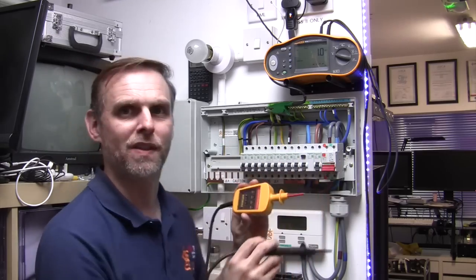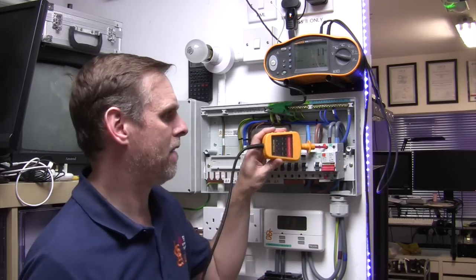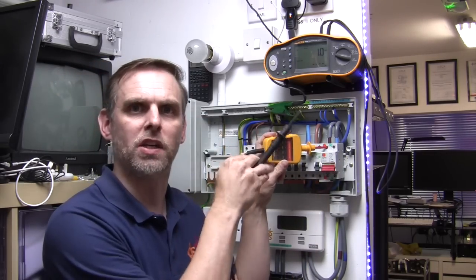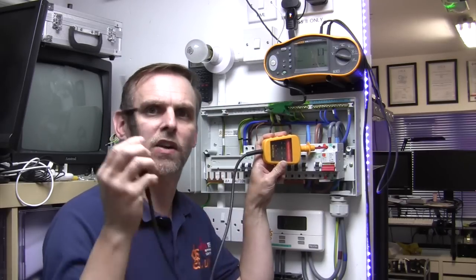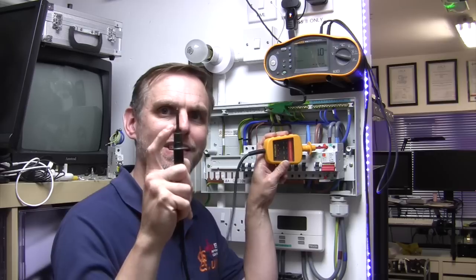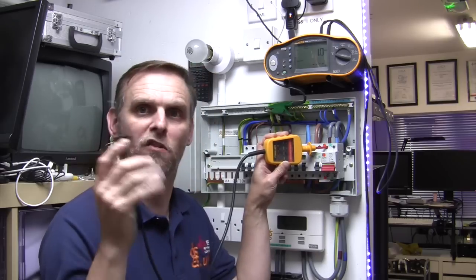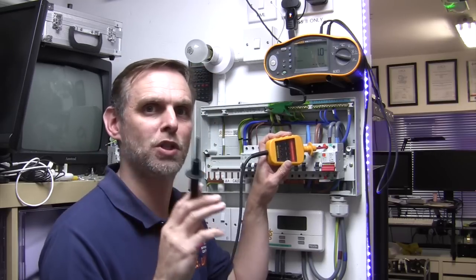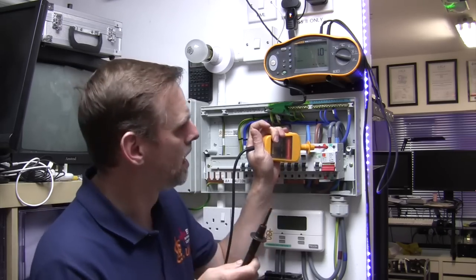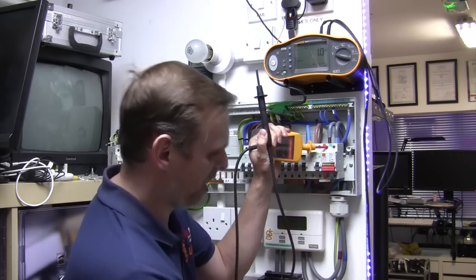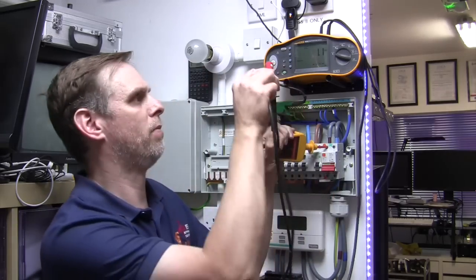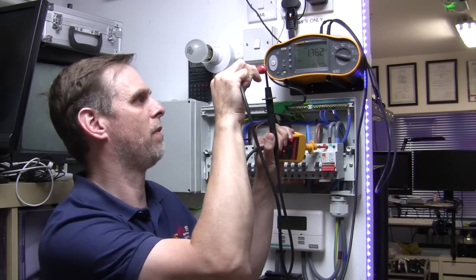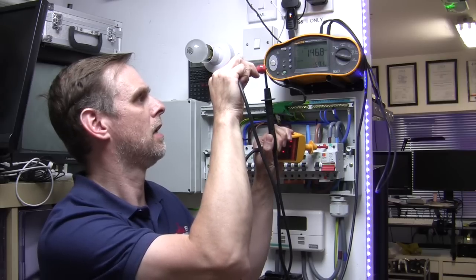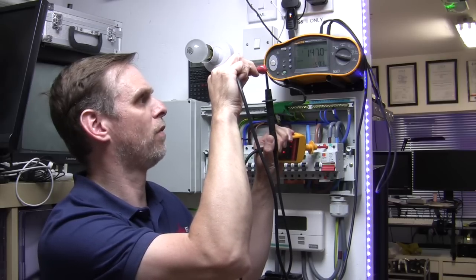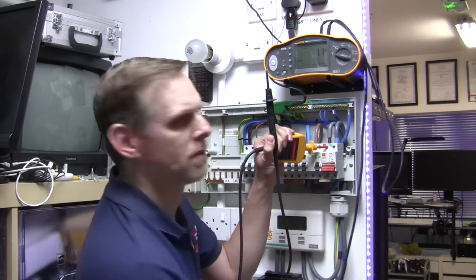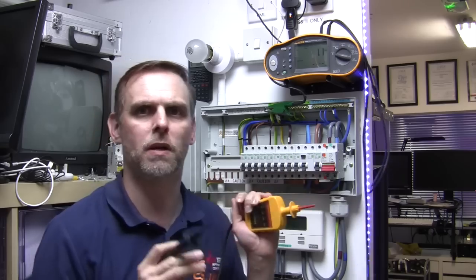Like this. The reason for that is that if we place this end of the probe onto the live part of the circuit, then the voltage will pass all the way through the indicator and all the way to the tip of the opposite probe. So this tip now has a voltage on it, which may itself be a shock risk if you do touch it. I can demonstrate that with my Fluke here, which I've got set to volts, by keeping my voltage indicator onto the live part there, and by touching the end of the probe with my Fluke's probe tip, and we can see we've got nearly 147 volts floating on the end of this black probe when this red probe has been applied here.